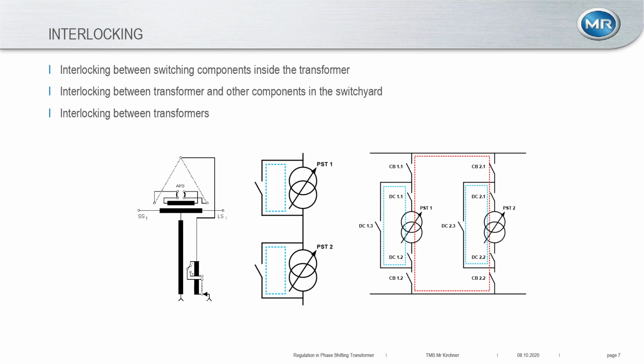the switchyard. And as we can see here on the sketch in the middle, that there is a bypass of these two transformers. And if you operate the bypass and the phase shifting transformer is not put to a neutral position, you basically have a voltage source that is short circuit by the bypass, and then you drive several kiloamps through this circuit, and this might not be good for your phase shifting transformer. So for that reason, it might make sense to have interlocking there.